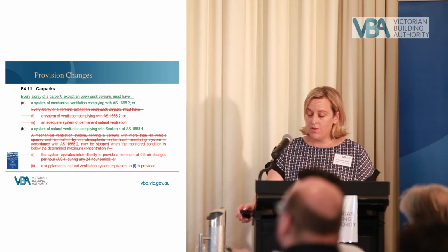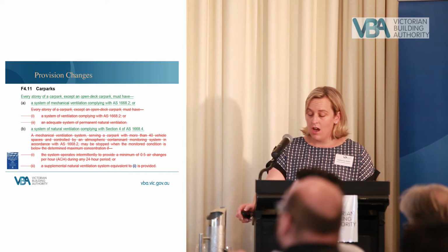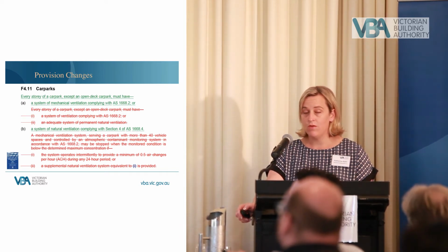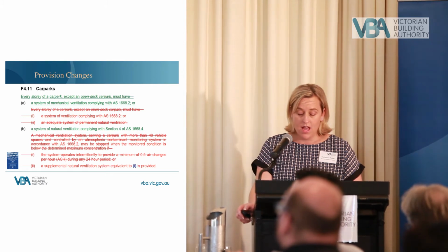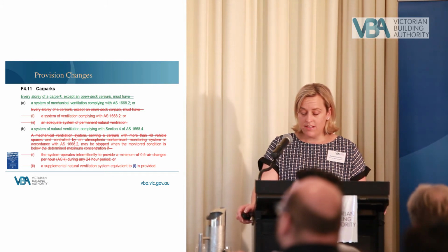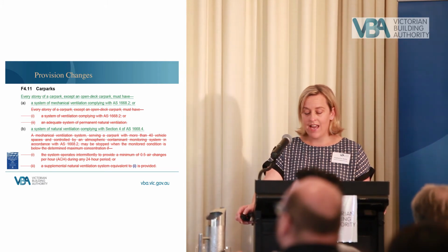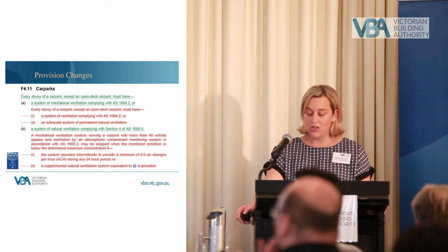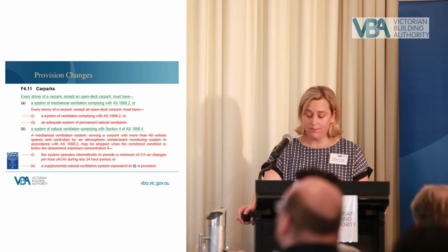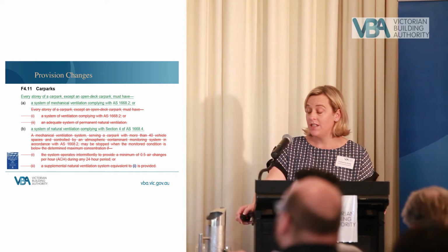This differs from the 1991 edition of AS 1668 Part 2, which included natural ventilation requirements for car parks. This means that sole references are now made to the 2012 editions of AS 1668 Part 2 for mechanical ventilation and Part 4 for natural ventilation.